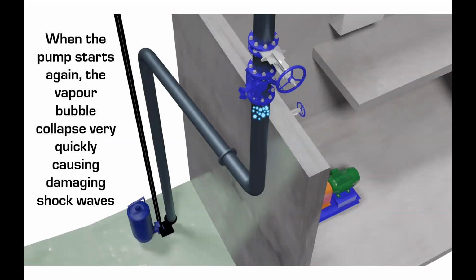So again, it's not even a submersible thing here. If you ever put the first check valve after the pump at values of 9 meters or so, atmospheric pressure essentially, then you could run into this issue. Secondary check valves after that will not have this issue. There are some standards to say, hey, don't put them too far apart as far as a height perspective goes, but it's that first valve that causes the issues.